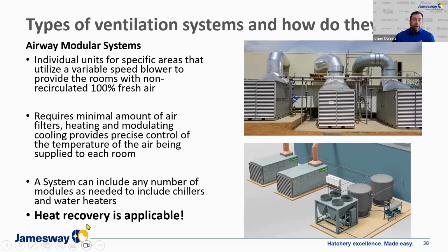And in addition to that, heat recovery is applicable with a system like this. So I can use that warmed return water from the incubation to preheat all of the outside air coming in to save on heating requirements for the facility. In addition, that warmed water can also be used to reheat air when you're functioning in dehumidification mode. So the energy efficiency is very applicable with heat recovery on these systems.